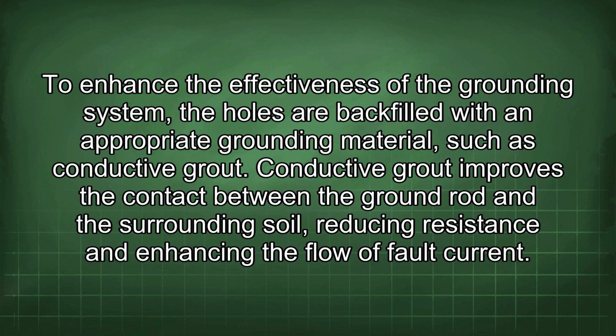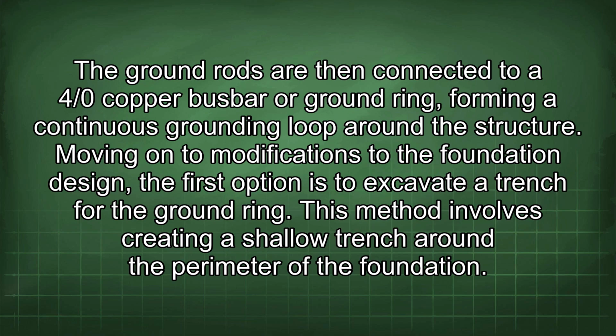Conductive grout improves the contact between the ground rod and the surrounding soil, reducing resistance and enhancing the flow of fault current. The ground rods are then connected to a 4/0 copper busbar or ground ring, forming a continuous grounding loop around the structure.